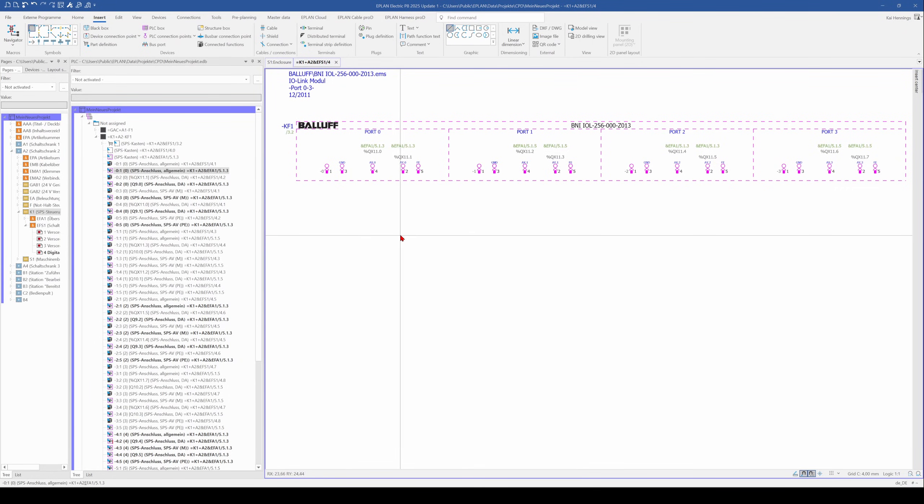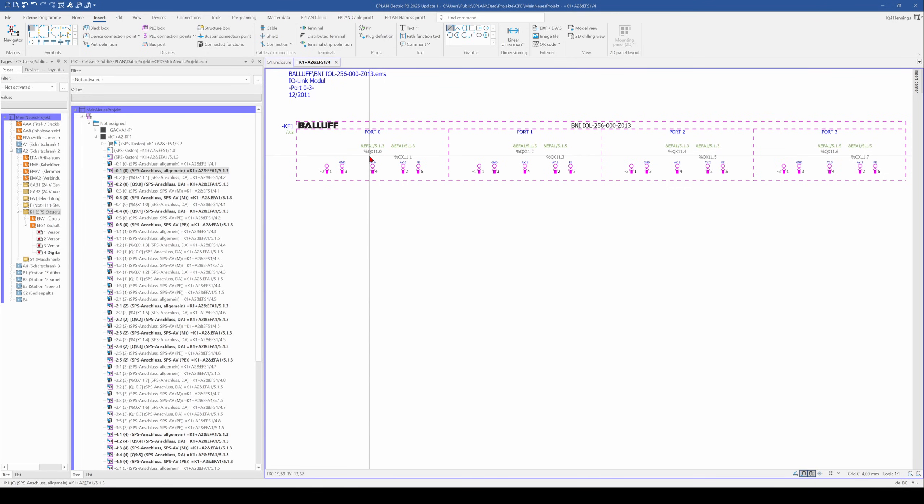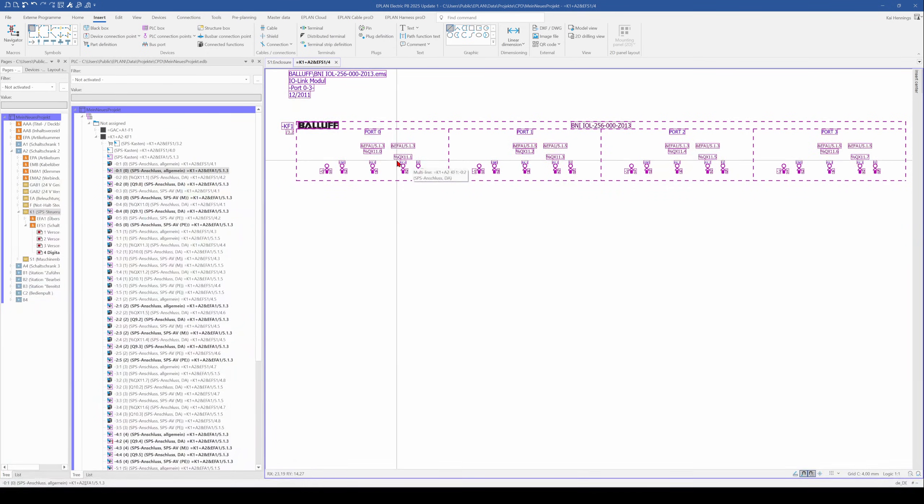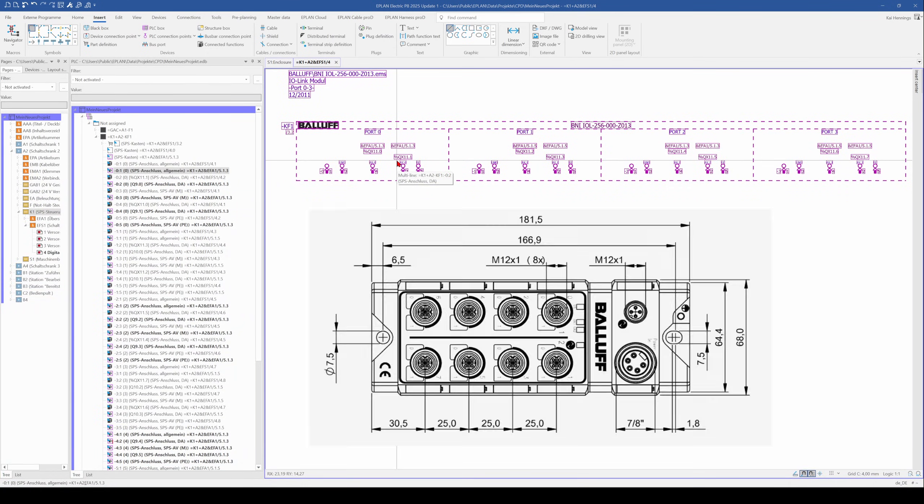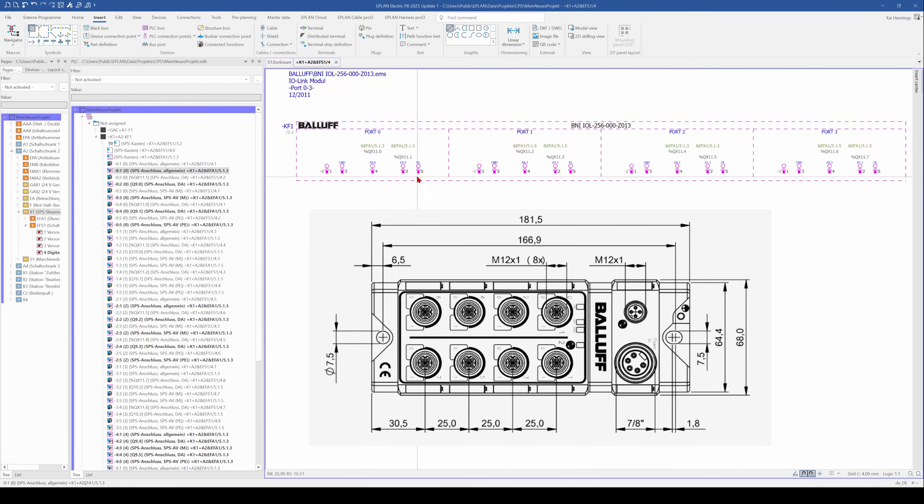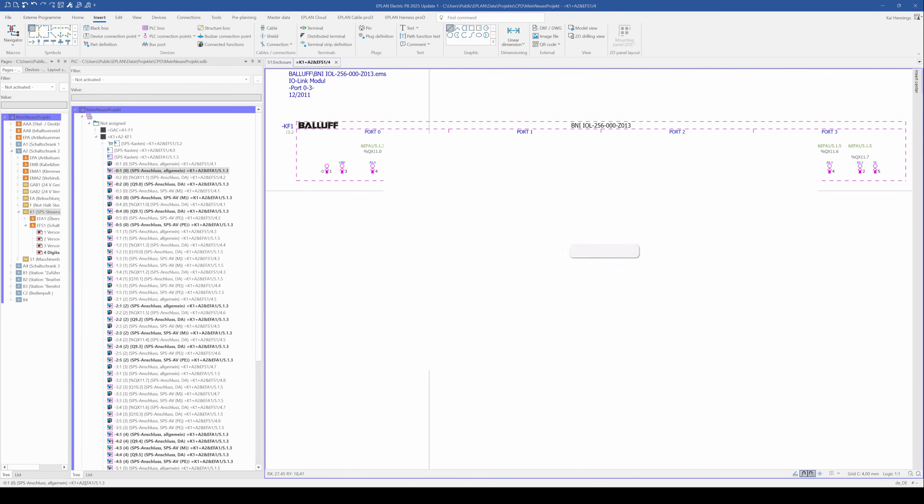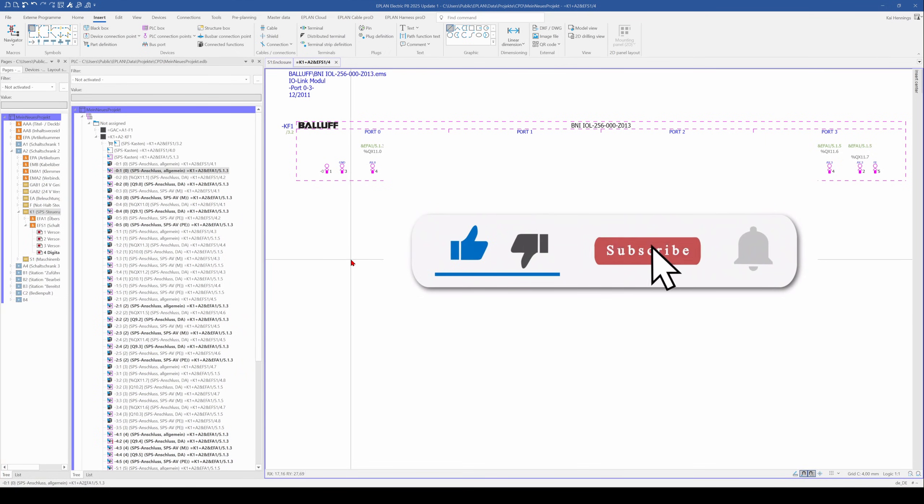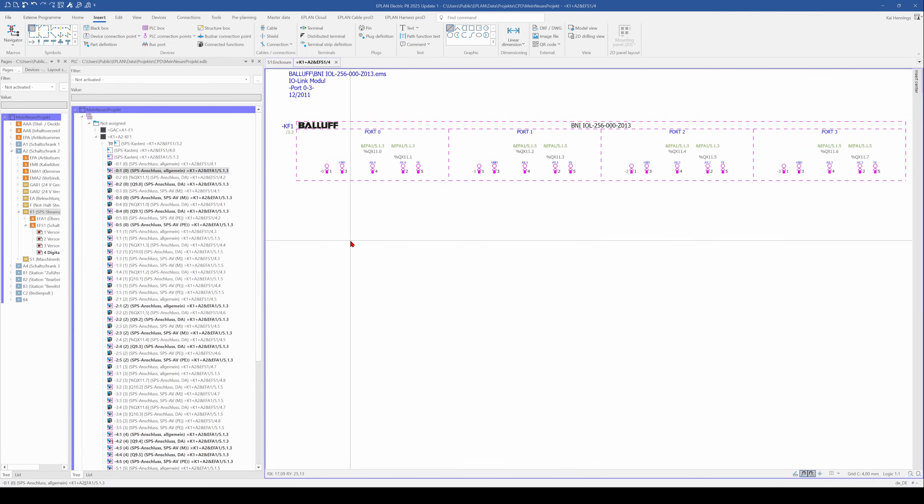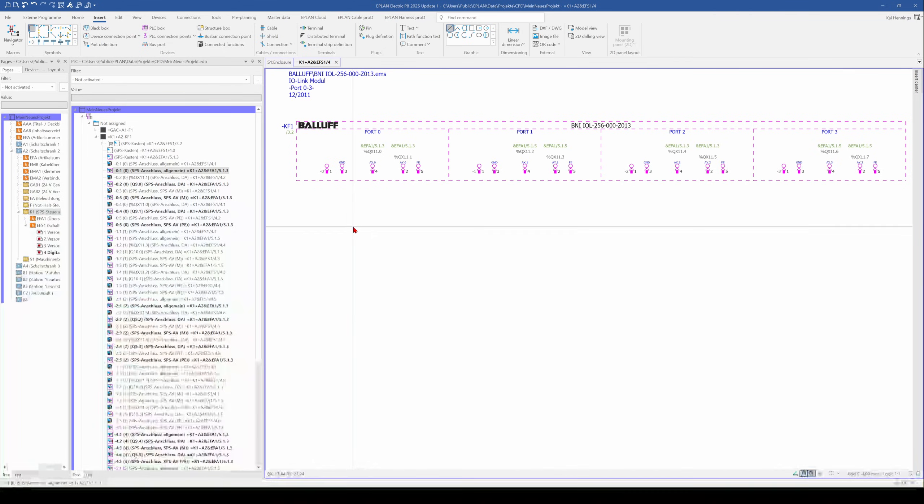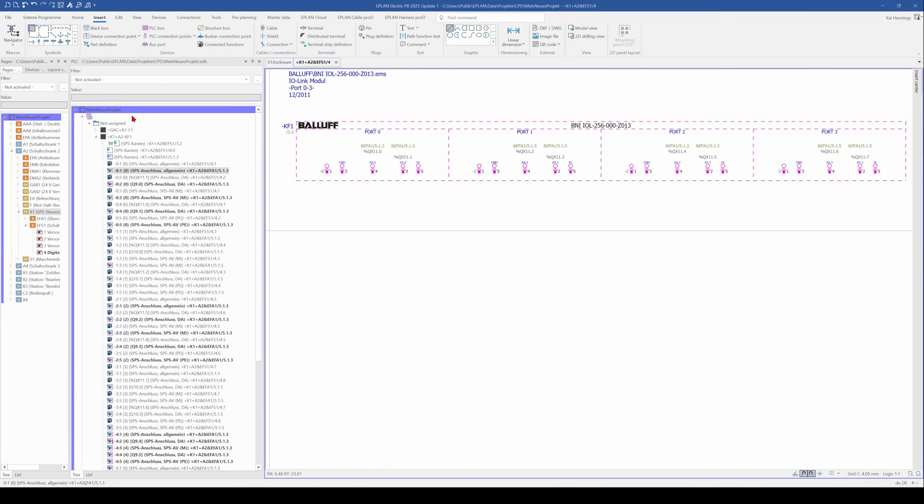What you can see here is one part of the multiline macro with the first four ports. This Balluff IO-Link module has in total eight ports and each port consists of an M12 plug. We want to have later on one PLC symbol which represents these five connections, and when we place it on our multiline drawing we want to have all of these in one go. So what we need in the first step is a digital output and we need to create a macro for this.